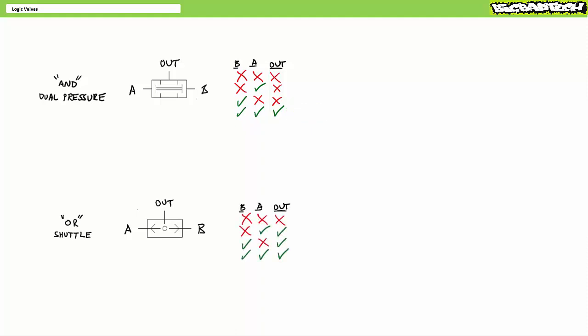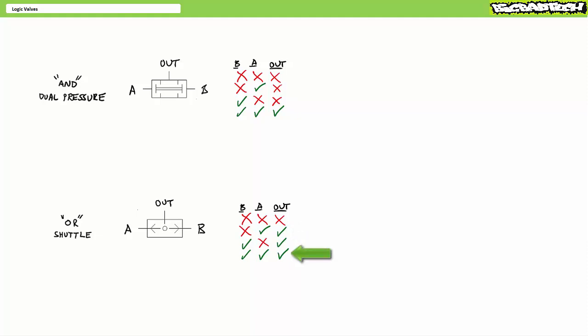In contrast, an OR or shuttle valve works like this: there must be a pilot signal at either input A or input B for there to be an output. When neither A nor B receive an air pilot signal, the OR valve produces no output. When only A receives an air pilot signal, the OR valve produces output. When only B receives an air pilot signal, the OR valve produces output. And finally, when both A and B receive an air pilot signal, the OR valve also produces output.